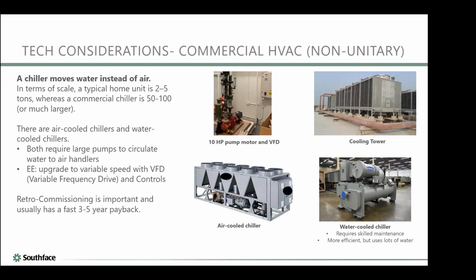One way to save energy with these systems is to make them true variable speed systems, where you have a variable speed chiller and convert your pump to a variable speed pump with a variable frequency drive, or VFD, shown in the top left picture. I'm pretty sure there are energy efficiency rebates available for that type of project.